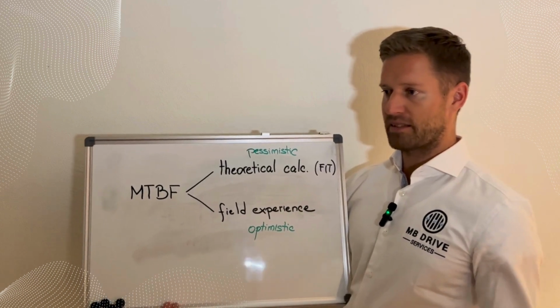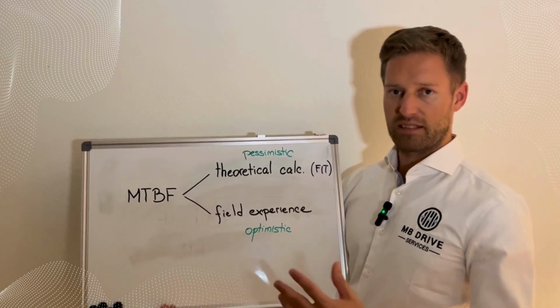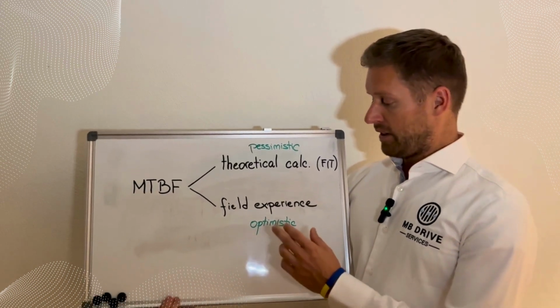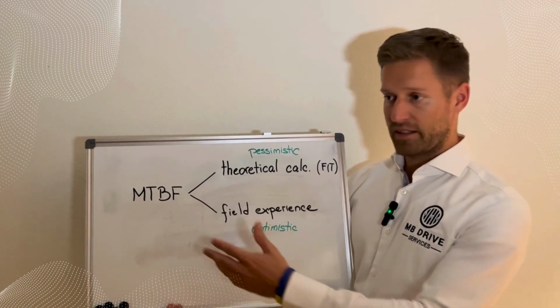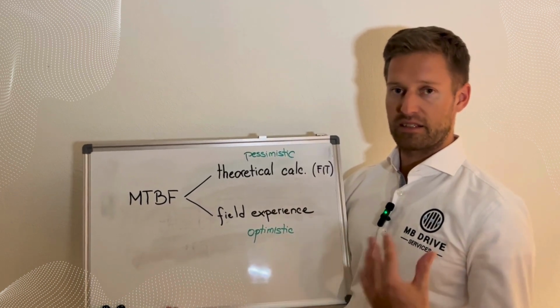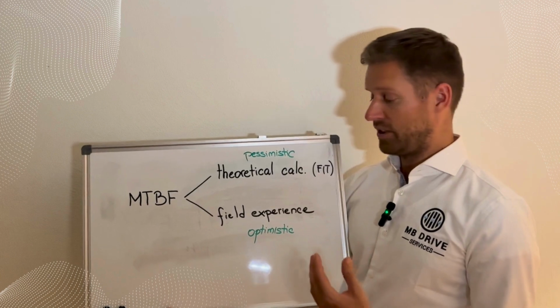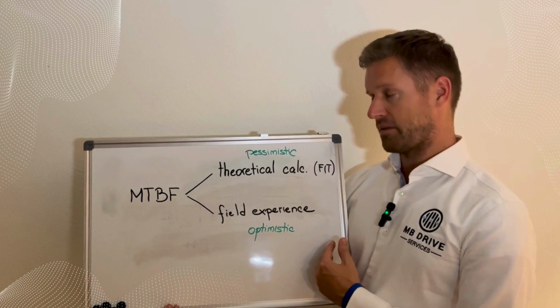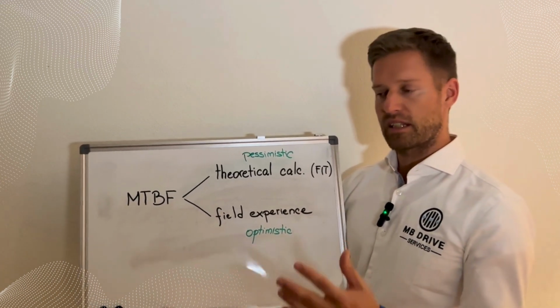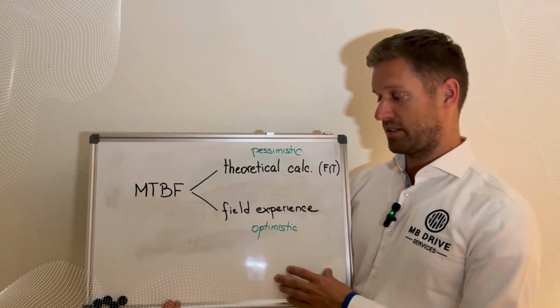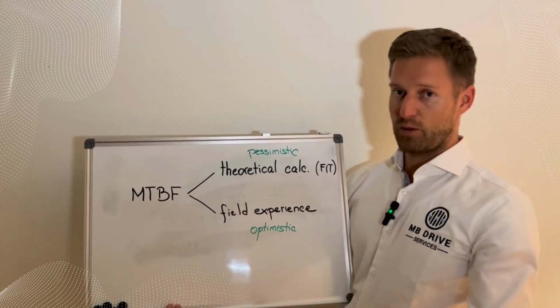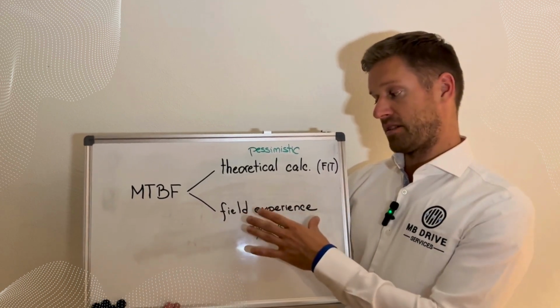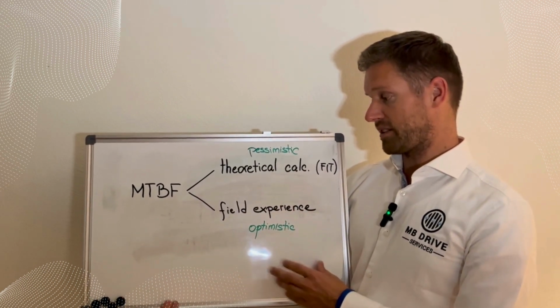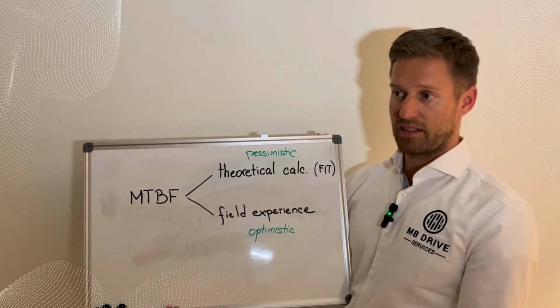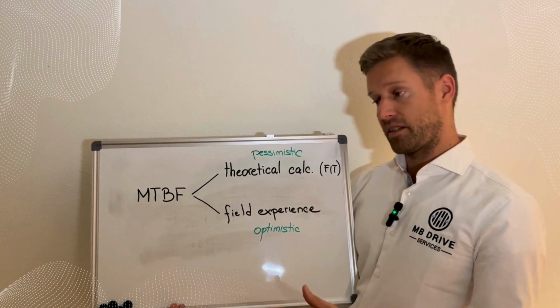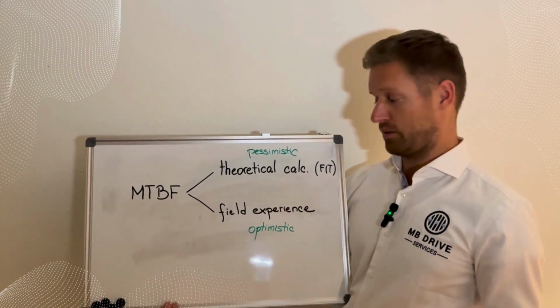But if the repair happens a long time after the warranty, it can be that the customer is rectifying the failure himself, or he is engaging some service company and the manufacturer might not get the notification that there was a failure. Nowadays, of course, if you have some remote monitoring system, then the manufacturer can see it. But if you have a large installed base, and especially older equipment, then maybe the monitoring system is not installed because it was not available at the time, or maybe some customers don't allow it due to cybersecurity topics and so on.